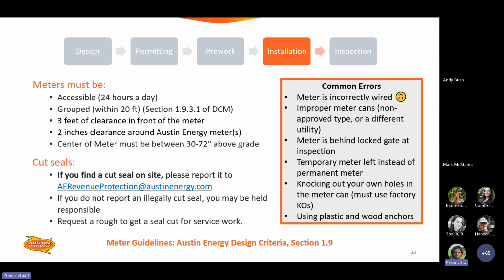When you do your assessment, you find from time to time that revenue meter seals have been cut and there's some unpermitted work that's happened. So that needs to be addressed and handled, and responsibility assigned to the proper party before you move on. And you can request a rough to get a seal cut for service work if you're doing service work on the PV meter.